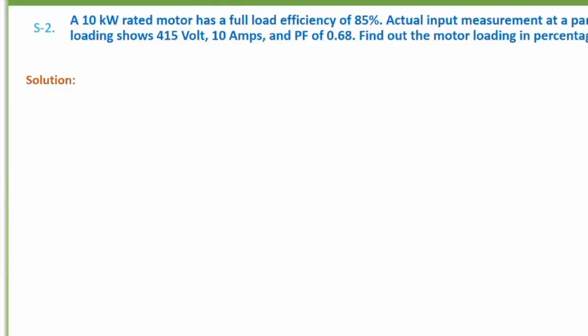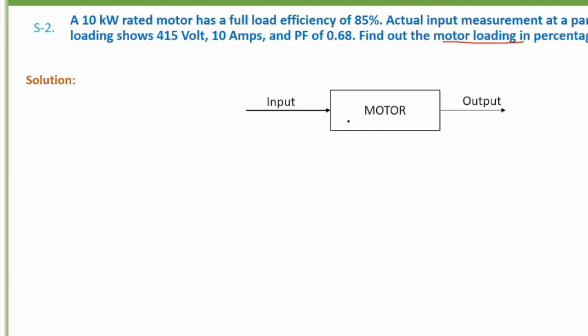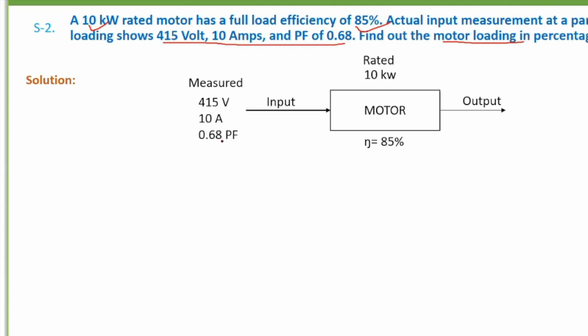This is from chapter three covering thermal and electrical energy fundamentals. Here is a five-mark question: a 10 kW rated motor has a full-load efficiency of 85 percent. Actual input measurement at a particular loading shows 415 volts, 10 amps, and power factor of 0.68. Find out the motor loading percentage. You can draw a diagram for practice and better understanding — a motor takes electrical energy as input and gives mechanical energy as output. The rated data given is 10 kW output with 85 percent efficiency, and the measured input data is 415 V, 10 A, and 0.68 power factor.